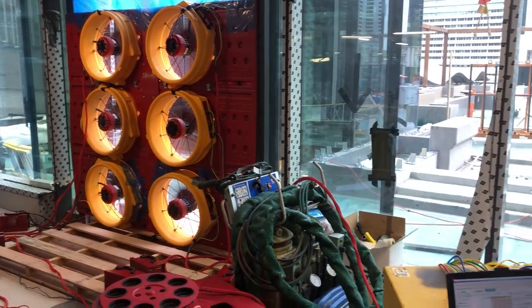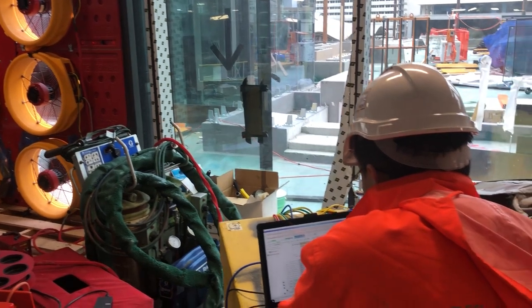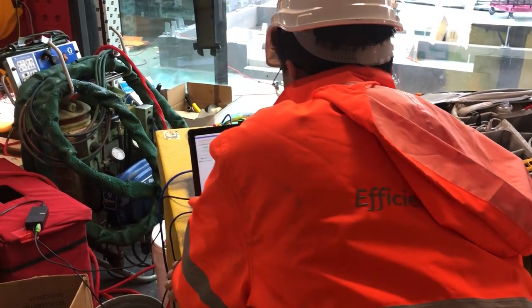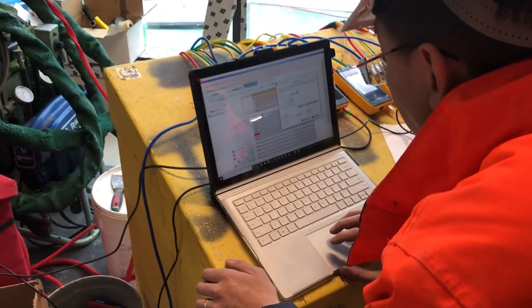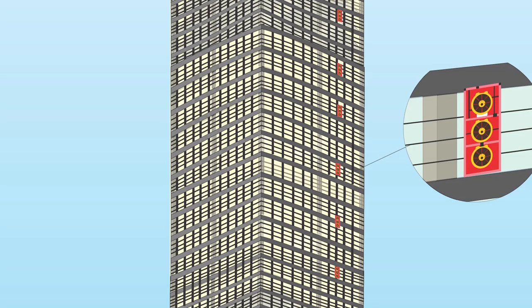So leakier buildings, no matter how many fans you've got, are actually, to a certain extent, impossible to test accurately. So a lot of the high-rise buildings are usually split up by a plant room. So they're basically a building on top of a building. And they're usually like HVAC zones. But Joseph, I'll let you go into compartmentalized testing, which isn't ideal, and that's where you use internal surfaces as an air barrier. The ideal case to deal with a large building is to test the entire building in one go with enough fans set up in a distributed fashion.